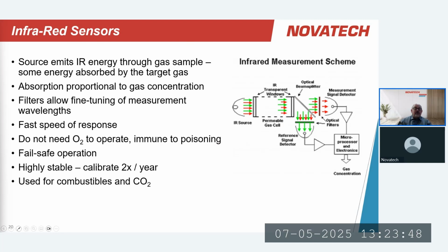And because of the type of wavelengths that we look at in the infrared spectrum, they are primarily used for hydrocarbons. So anything that has the carbon-hydrogen bond, methane, ethane, propane, things of that nature. Generally speaking, not very, very large molecules. Once the molecules get larger, the interactions with the infrared spectrum become much more difficult to manage. So smaller hydrocarbon molecules and carbon dioxide.